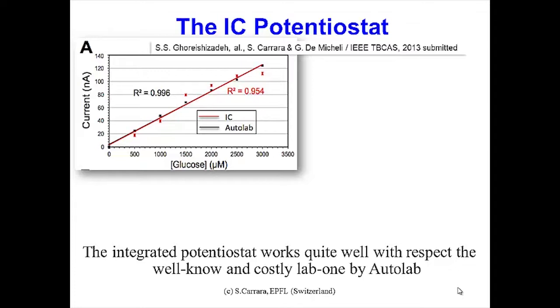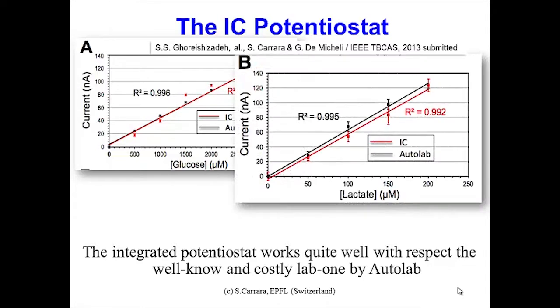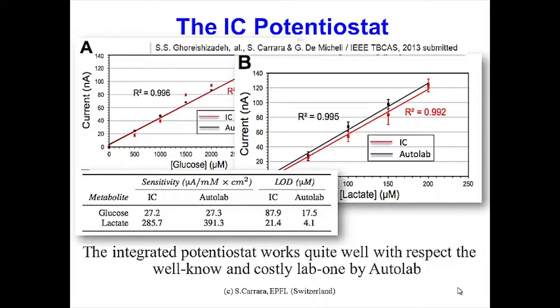We did it for glucose and also for lactate. In both cases, these are chronoamperometric measurements, fixed potential measuring only a current that varies with concentration. We obtained quite good correlation between the measured sensitivities, while we are worse than expected in the limit of detection, mainly due to more noise in our integrated potentiostat.